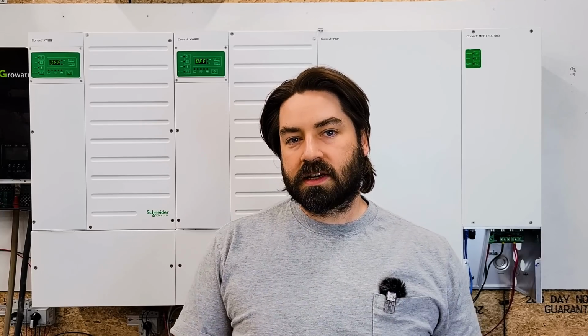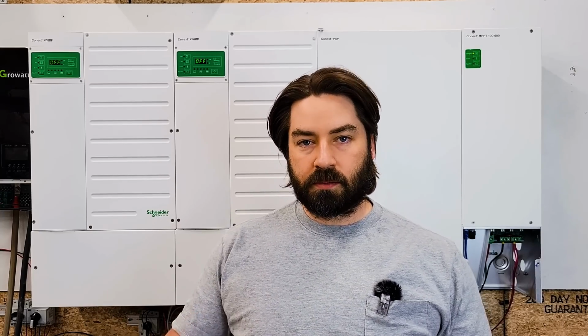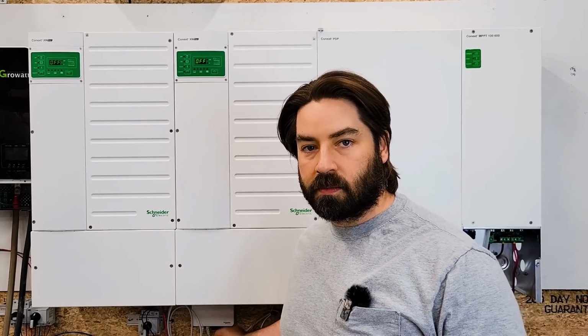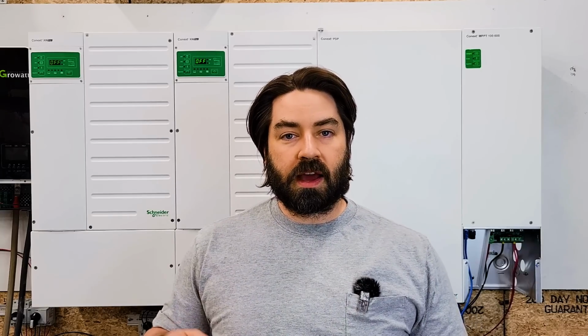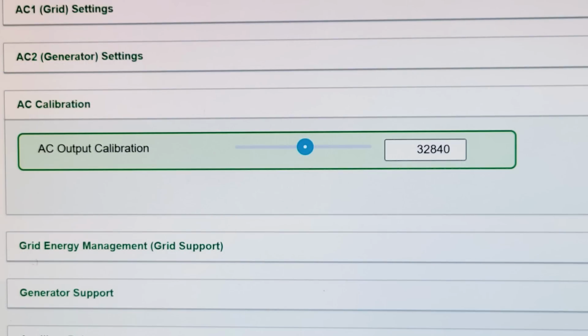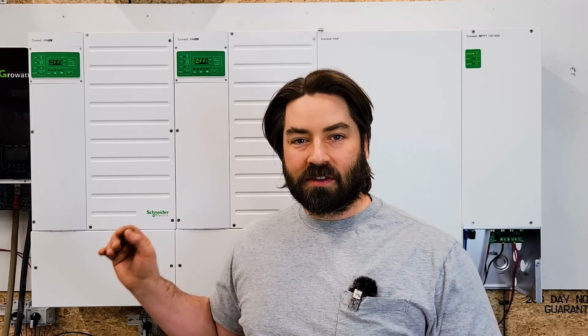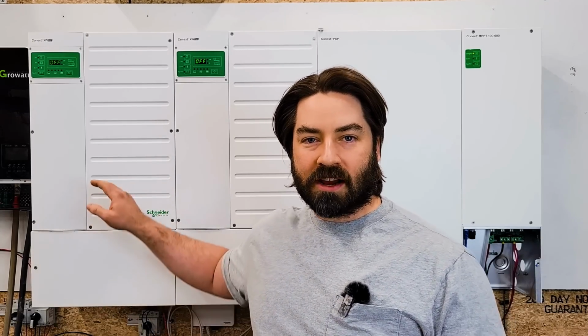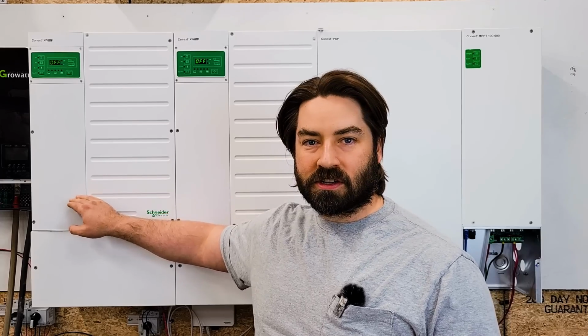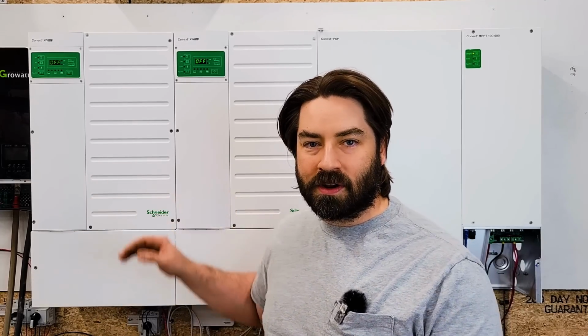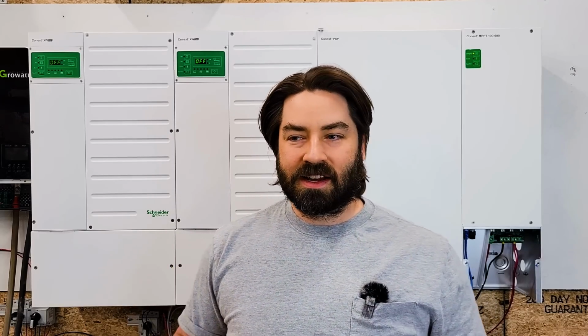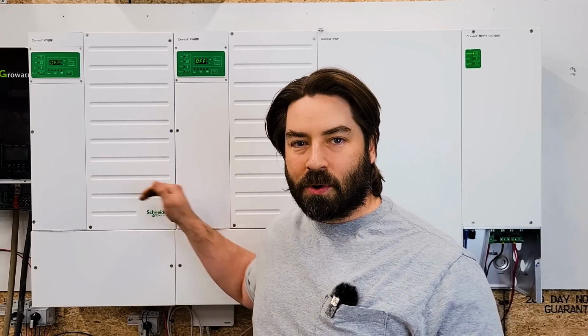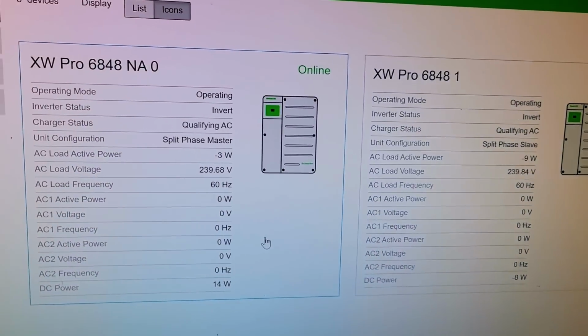So by going into the Insight Home, which means opening up the Insight Home on a computer, you then go to the advanced settings and it's AC output calibration. Now this is a 32,000 number. It was like 32,700 or something. So by adjusting that 32,000 number up or down, we can adjust the output voltage slightly. And the goal is to get them to output the exact same voltage. So I brought them both up, and now they're outputting the exact same voltage.